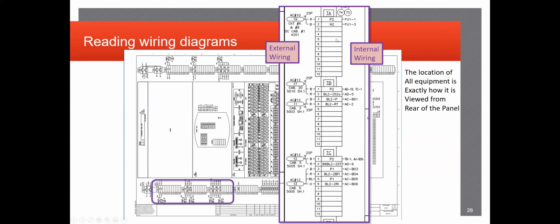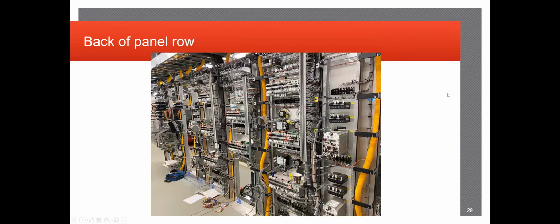Determining on these wiring prints as well which side is external and internal is usually fairly straightforward. The internal stuff is associated primarily with stuff that's going into the cabinet, whereas the external stuff is going to have cable numbers, designations, and what type of conductor. In this case, up here, this would be for conductor number 10 with 2 spare wires, number 19, and cable designation, et cetera, et cetera.